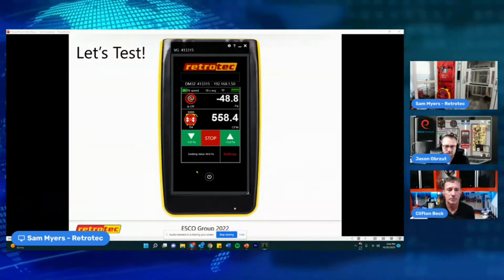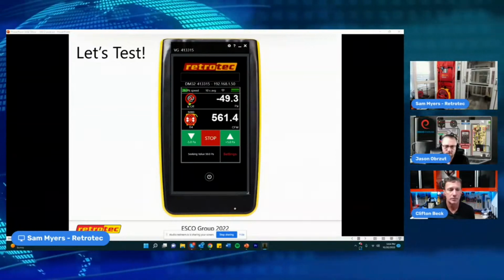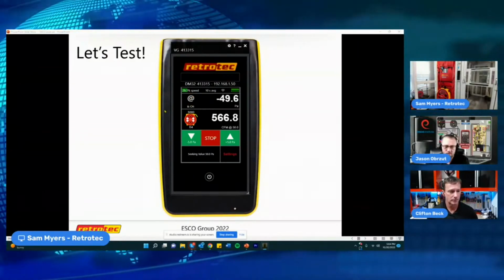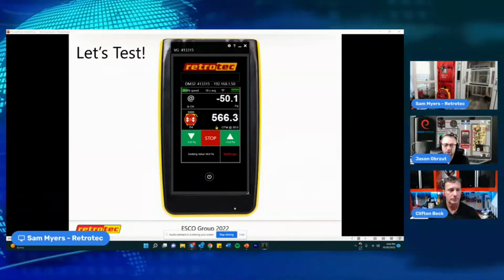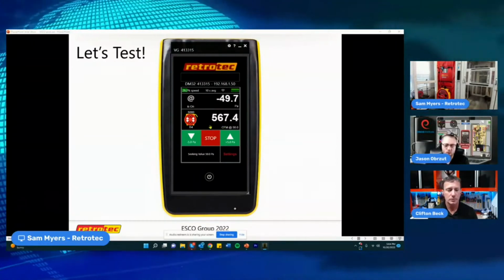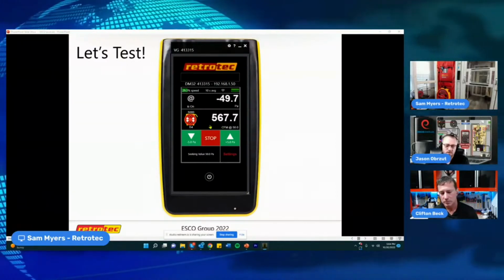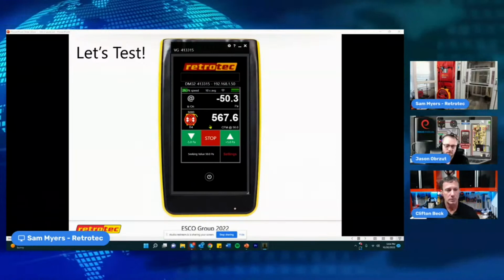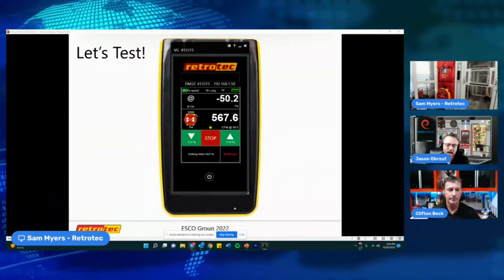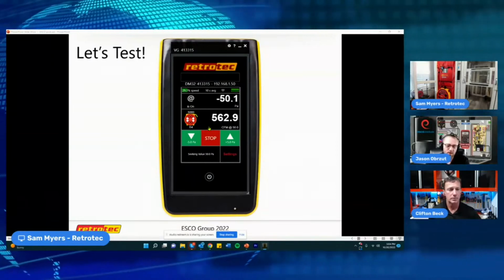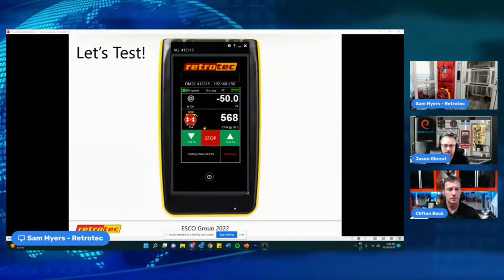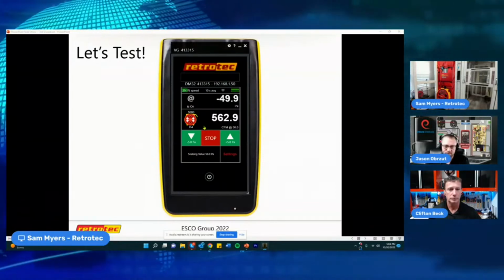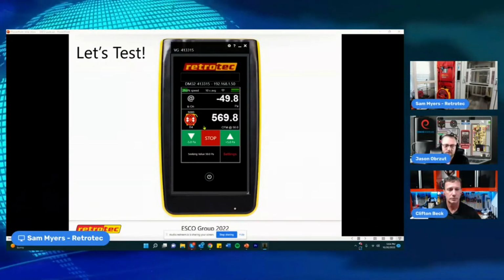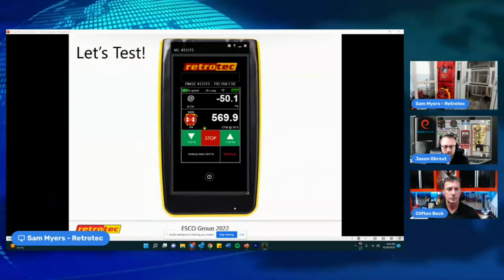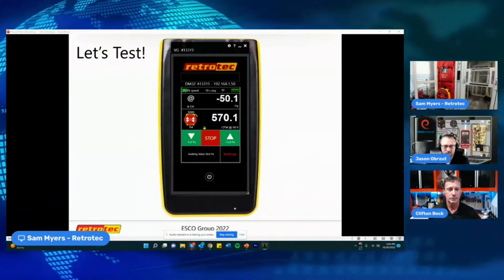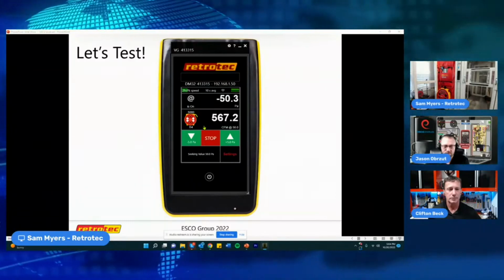If I have the fan wide open and still can't reach 50, but I'm close, we've got a button you can click to extrapolate the reading. So let's say you're only getting to 40 and it won't go further, running wide open, I can tap that button and it'll tell me what it would be if it could have reached 50. In a very leaky building that would be pretty helpful. But if you can only get to like 20, it's not going to be accurate. You want to be at least somewhat close to that 50 Pascal target, usually within 15 Pascals. So if you can get to 35, it's good, but below that, I really wouldn't trust the reading.